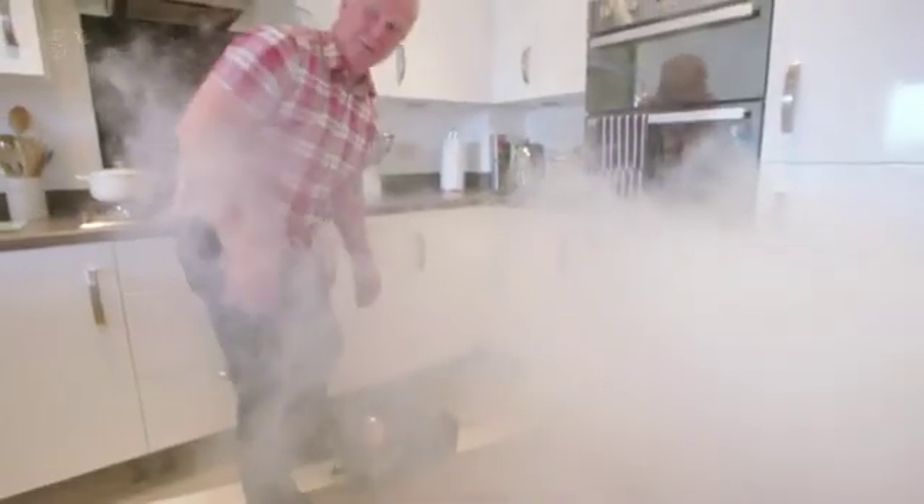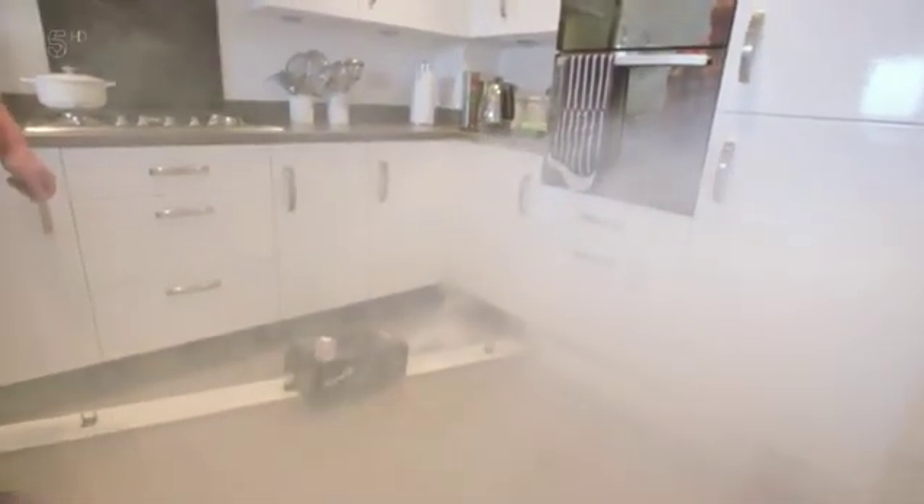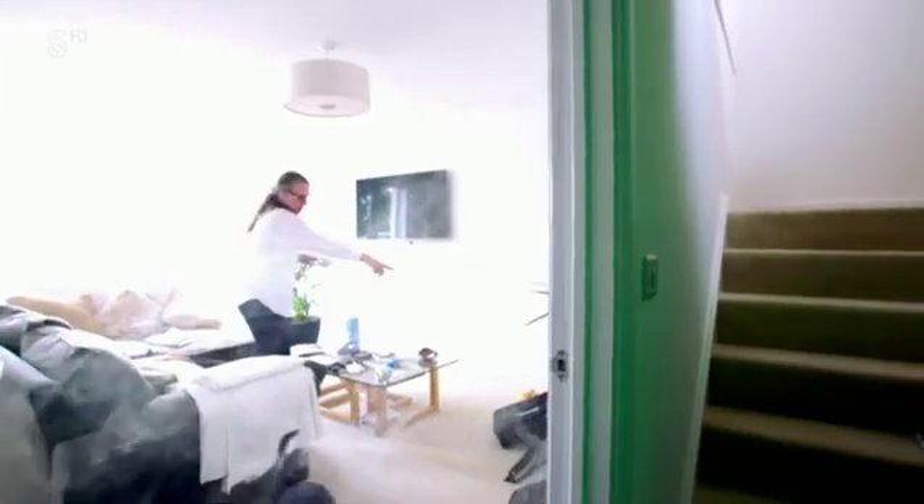There are no building regulations about sealing boxing for pipes, but it is listed as an NHBC standard, so should have been checked. If the area is adequately sealed, the smoke will remain trapped and confined in the kitchen. But that's not the case here. The smoke has quickly spread to other rooms throughout the three-storey house. If this was a fire, it could have potentially spread across two of the three floors in a very short time.